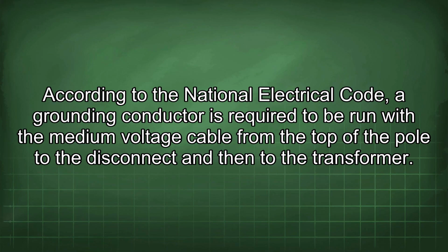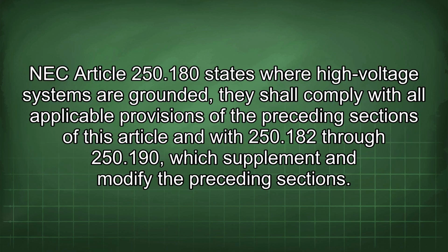According to the National Electrical Code, a grounding conductor is required to be run with the medium voltage cable from the top of the pole to the disconnector and then to the transformer. NEC Article 250.180 states where high voltage systems are grounded, they shall comply with all applicable provisions of the preceding sections of this article and with 250.182 through 250.190, which supplement and modify the preceding section.